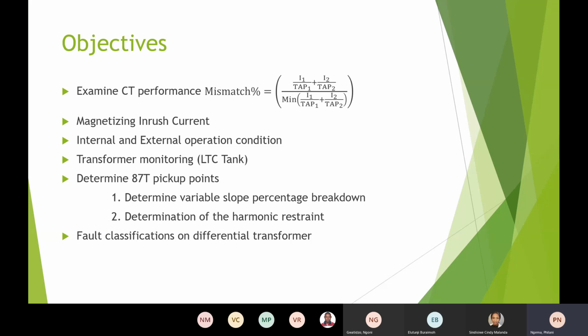So the first point is to ensure that the CT performance on the differential protection is accurate and correct, so that we will not experience the errors caused by the CTs, the current transformers. Then the magnetizing inrush current, which is one of the big problems caused by the energizing of the transformer. When energizing the transformer, they only find that the relay sees a fault, because the magnetizing inrush current is very high. It's about 8 times the full load current. So it's one of the issues that need to be addressed: how to make sure that the relay is able to differentiate between the fault and the inrush current.